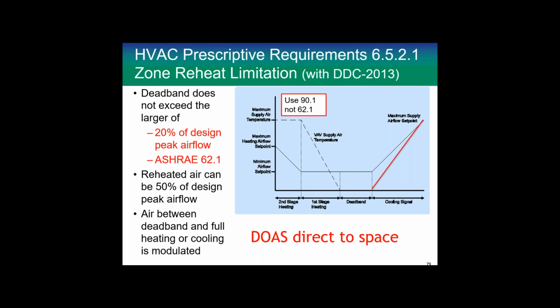And then suppose you were using a DOAS and you were supplying the air directly to the room from your DOAS, which is one of the ways they do it. I do a lot of defense work for the DoD, and the DoD pretty much requires you to use a DOAS directly to the room. So if that happens, then you can go to zero set with your normal VAV box because it doesn't have outside air in it at all. It's not controlling the outside air. So if you're going direct to space, you can go to zero set point on your box, since it's not required. And then you can come over to here to where you need heating, and then you can start opening back up. But you won't have to do this dead band at velocity or with flow.